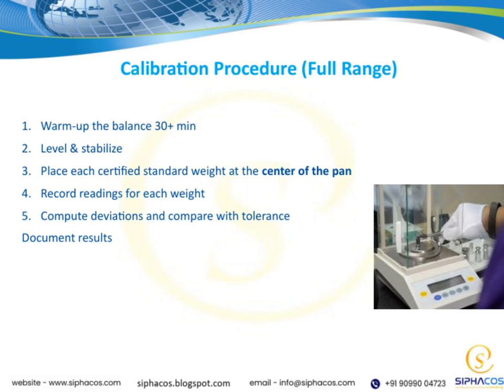Next, you'll place each certified standard weight at the center of the pan. Center placement is key because it ensures the weight is fully supported and balanced correctly. After placing each weight, record the reading displayed by the balance. It's important to do this for all the weights in your calibration range. Once you have the readings, you'll compute the deviations between the displayed value and the known weight. Comparing these deviations against the allowable tolerance helps determine whether the balance is performing within acceptable limits.